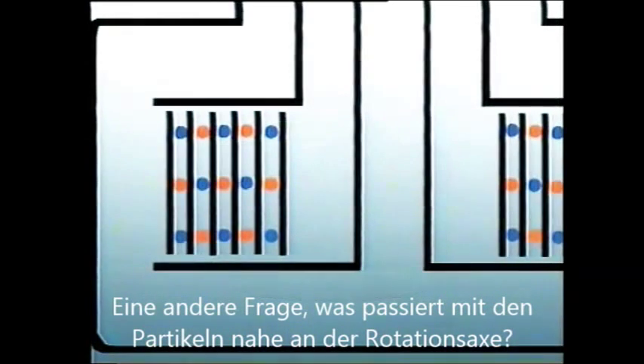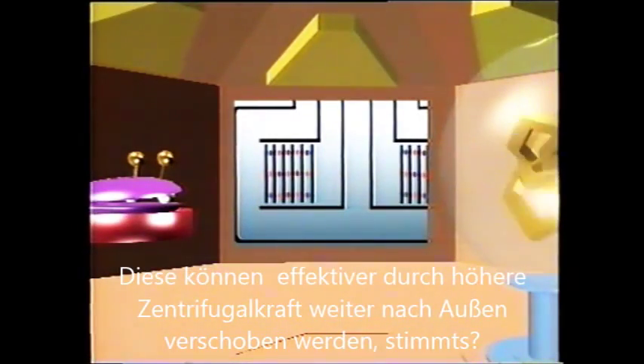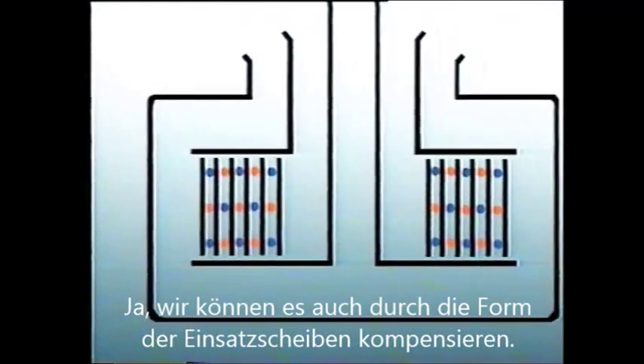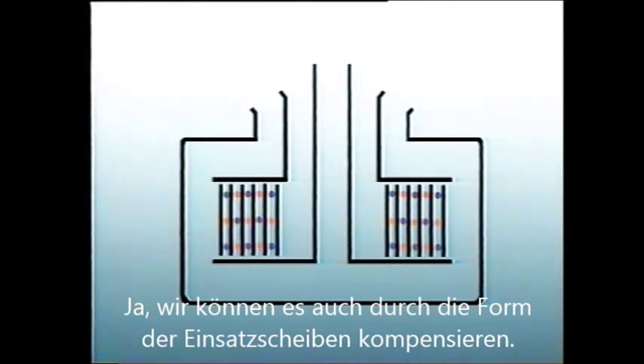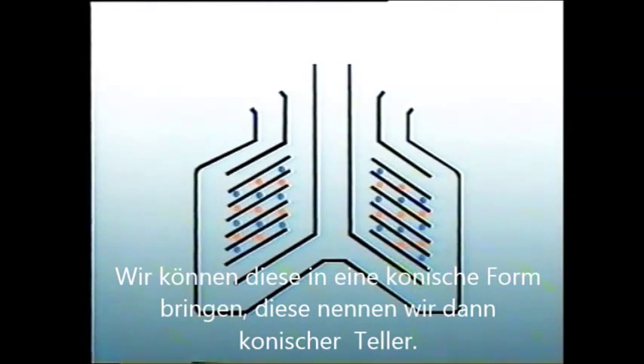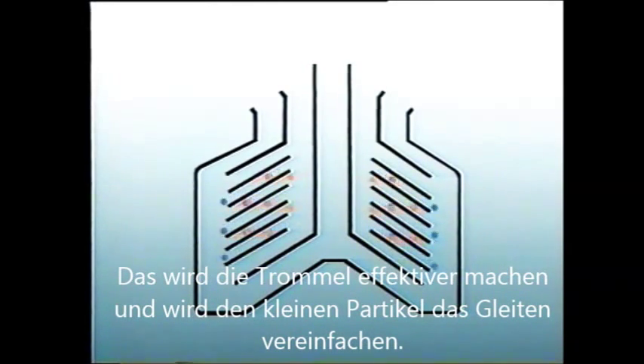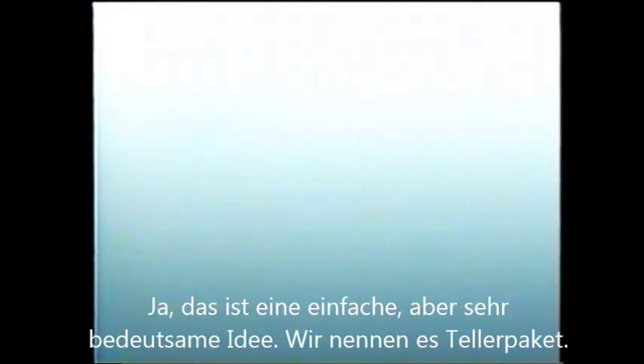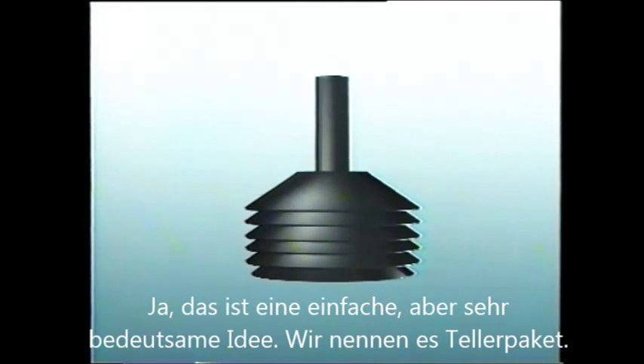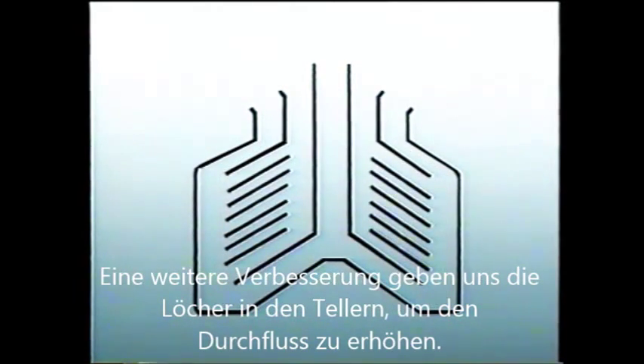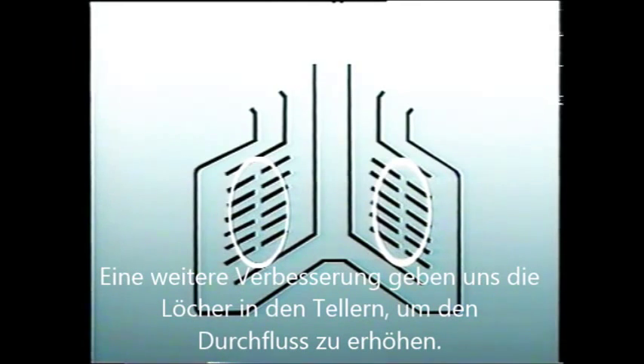What will happen to the particles nearer the center of rotation? They'd be subjected to a smaller, less effective centrifugal force. So could we compensate for this in the shape of the cylinders? We could turn them into conical disks and alter the shape of the bowl accordingly. This will make them more effective and also allow the particles to slide in the direction they have to travel. This is what is called a disk stack.